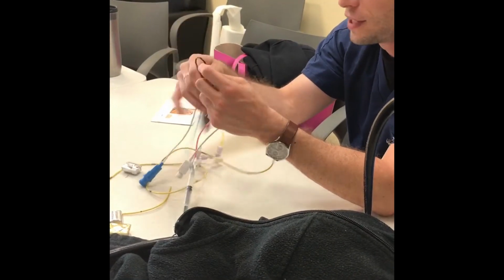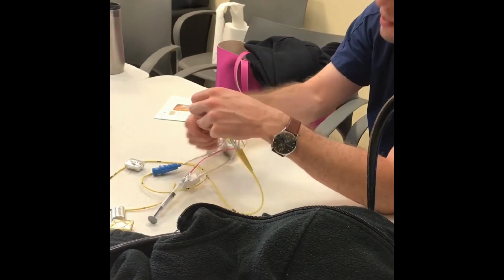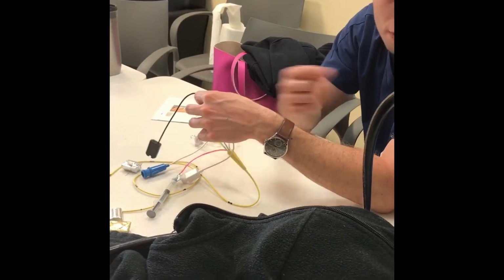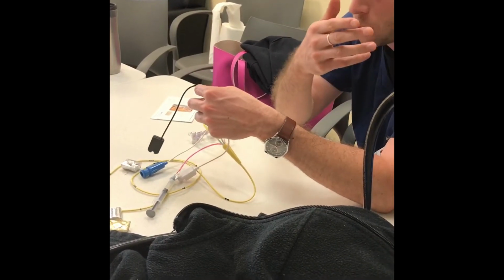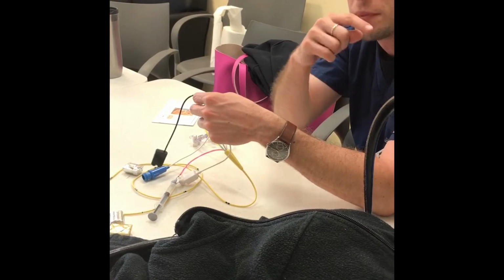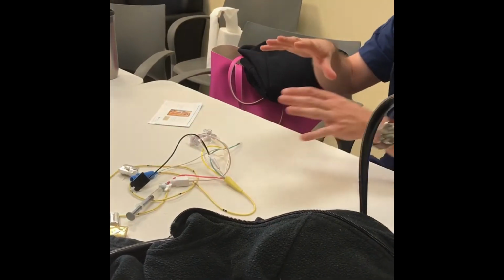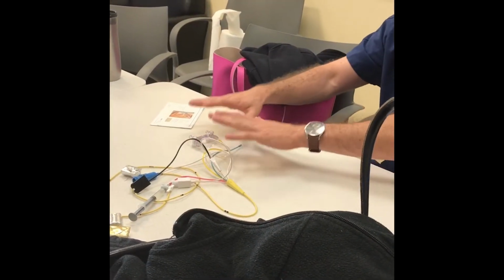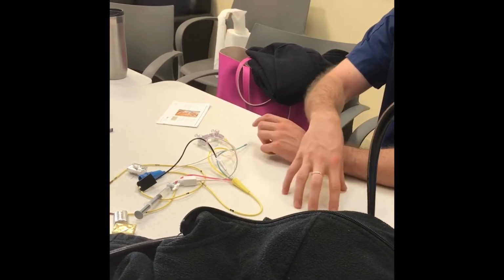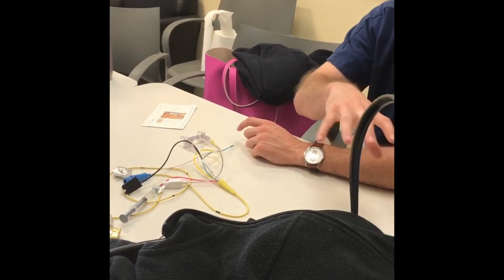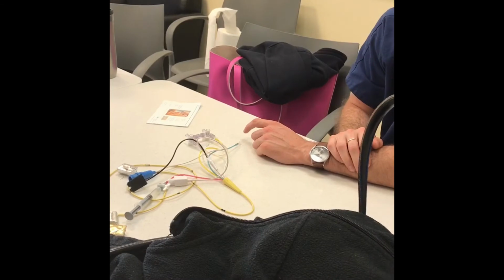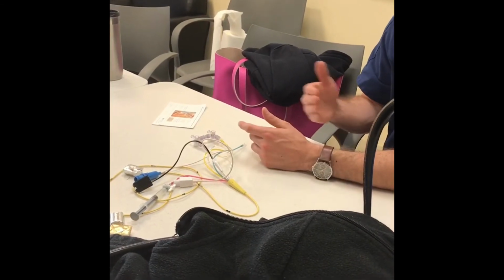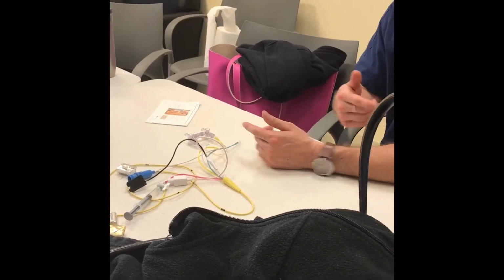Okay, I'm not telling you you can't bend it like that, but if it's bent, you could bend the optics in here, and that number won't potentially show up, or it'll be off. And there's ways to, so just so you know too, again with the cardiac output, I've just told you the ways to check it. With the SVO2, when I go into it, there's ways that we tell you, or the monitor tells you, whether the number is accurate. All right? Okay. So if you're wondering why something's looking off, you'll have ways to look.